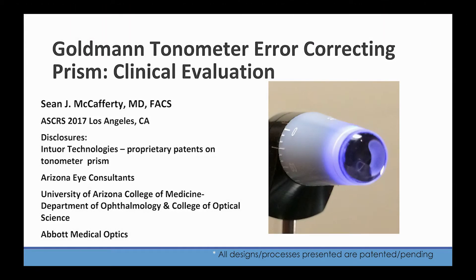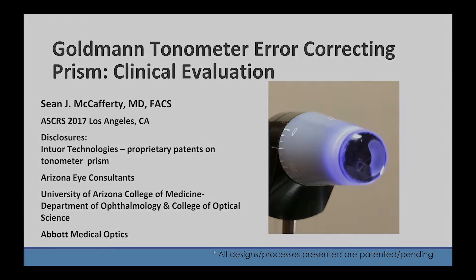The purpose of the study is to evaluate a correcting applanation tonometry surface, or CATS prism, in the clinical setting validating previously published mathematical modeling. This mathematical modeling showed a significant decrease in corneal biomechanical errors.